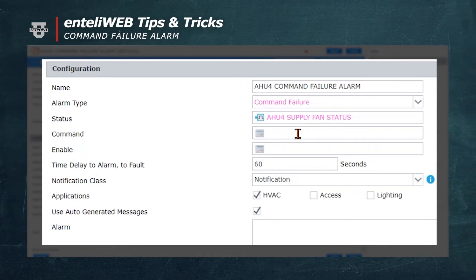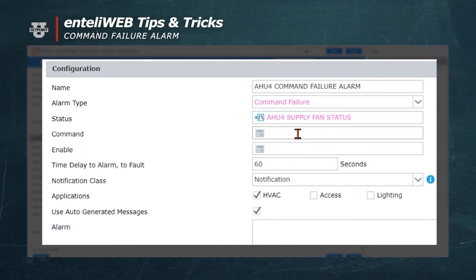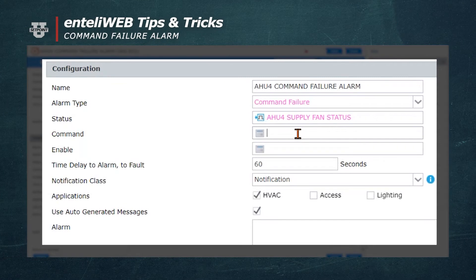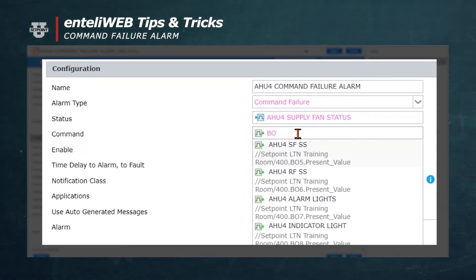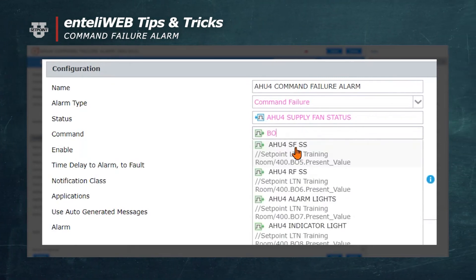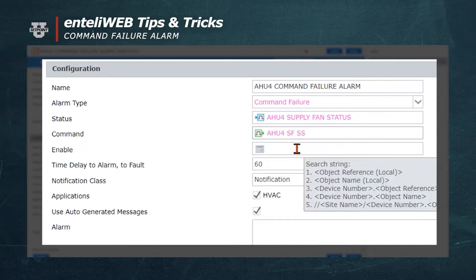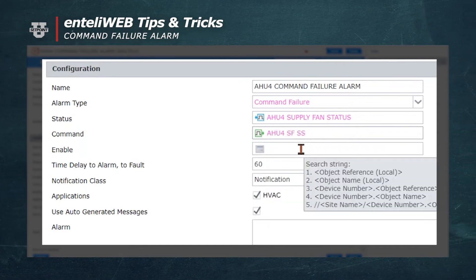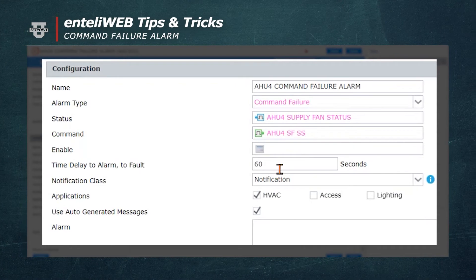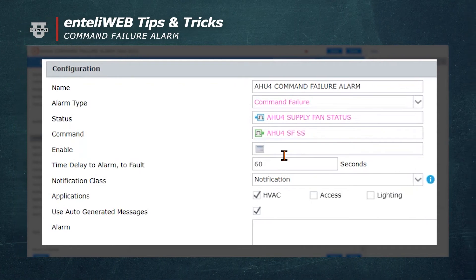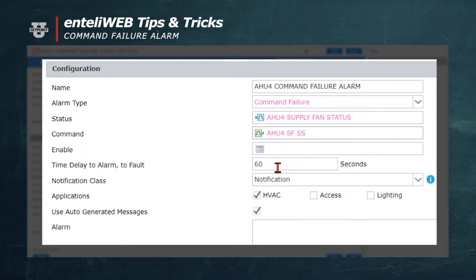The next block asks for the command — are we commanding it to run or are we commanding it not to run? I'll put Binary Output 5 for the start/stop of the unit: AHU4 Supply Fan Start Stop. I'll leave the enable function blank so the alarm is active all the time.